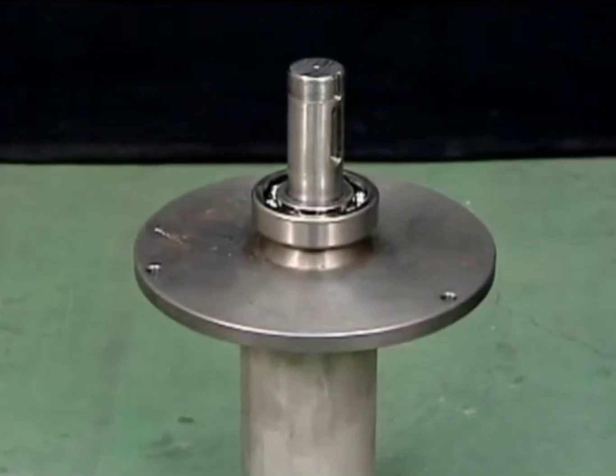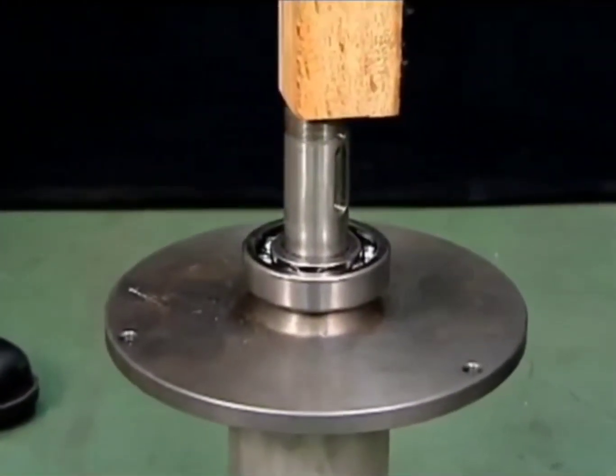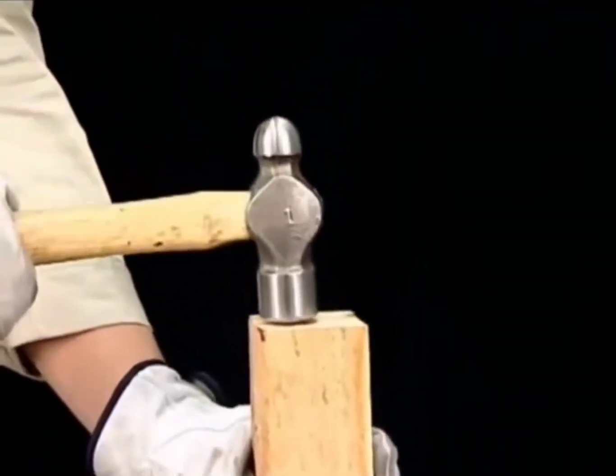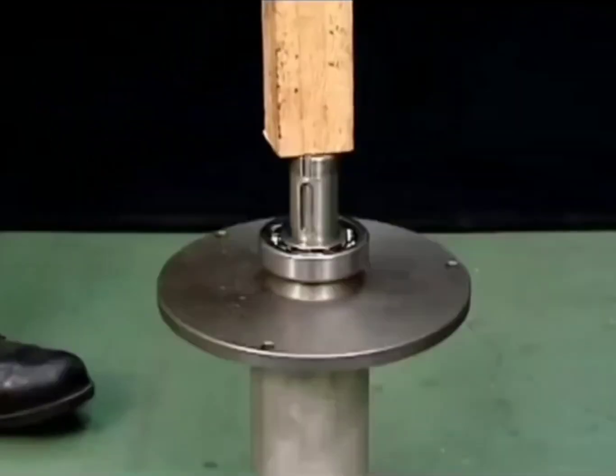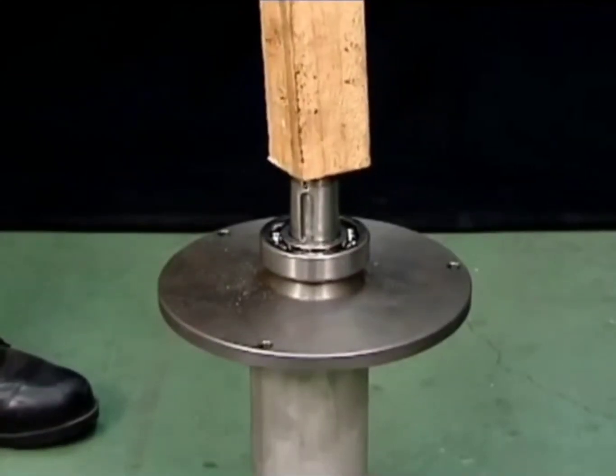Support the gear boss with a pipe or similar item and place a wooden slat against the friction pulley of the horizontal shaft. Then tap lightly to release the gear boss. This completes the disassembly of the horizontal shaft.